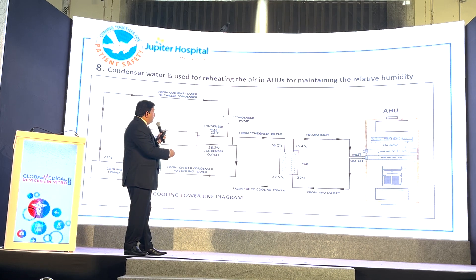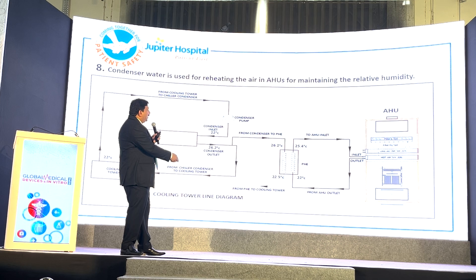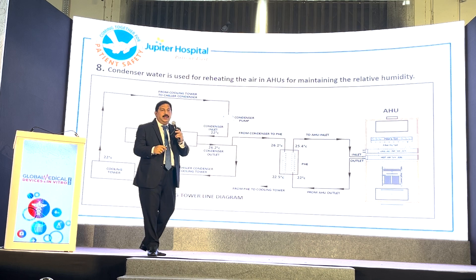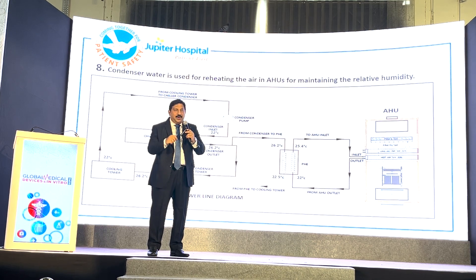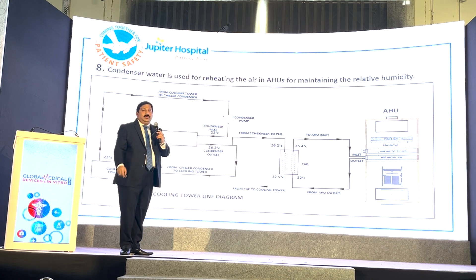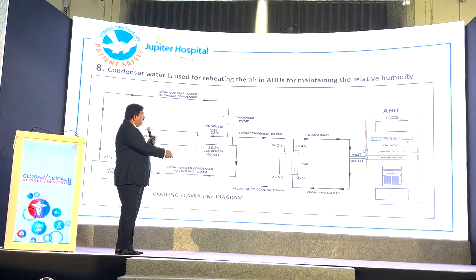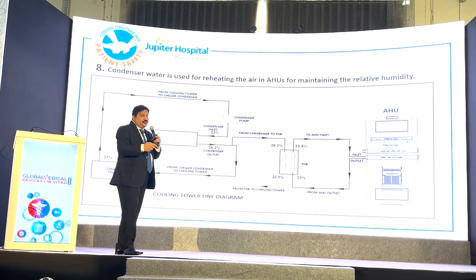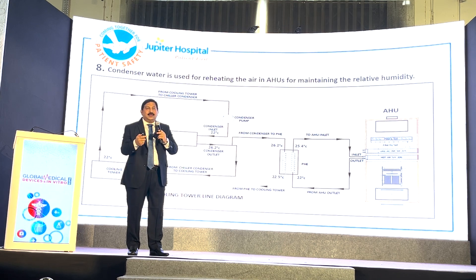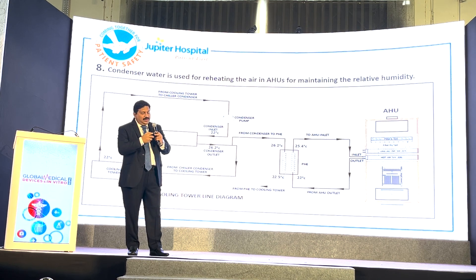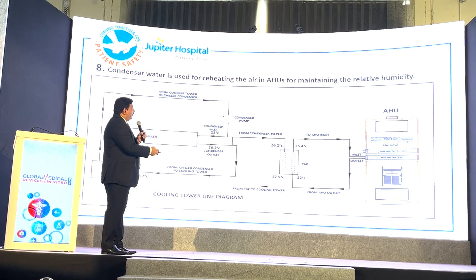We have used this 25.4 degree chiller by-product water for controlling humidity. So our chiller is doing dual work — one is cooling, and as a by-product the hot water being circulated is used for the AHU. In our Pune hospital, everything has to happen from day one. It cannot happen as a retrofit, because in a running hospital, doing something retrofit is not easy. So we have controlled with this.